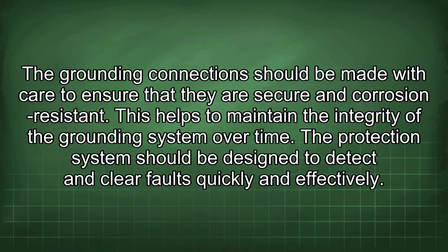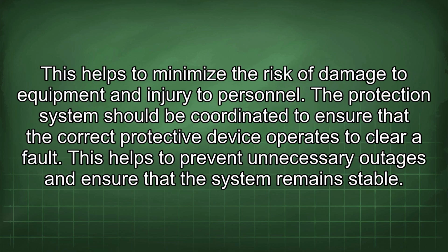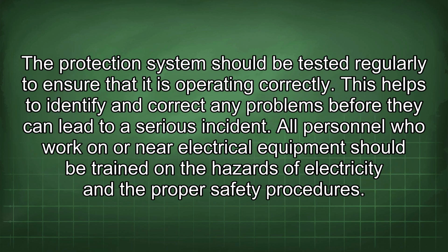The protection system should be designed to detect and clear faults quickly and effectively. This helps to minimize the risk of damage to equipment and injury to personnel. The protection system should be coordinated to ensure that the correct protective device operates to clear a fault. This helps to prevent unnecessary outages and ensure that the system remains stable. The protection system should be tested regularly to ensure that it is operating correctly. This helps to identify and correct any problems before they can lead to a serious incident.